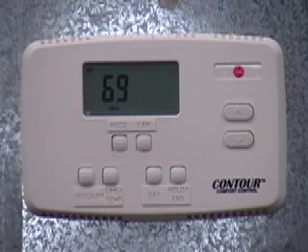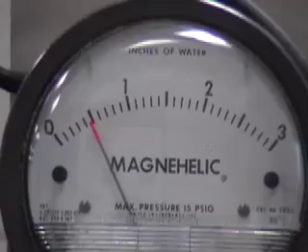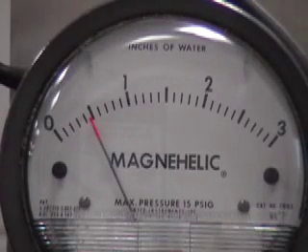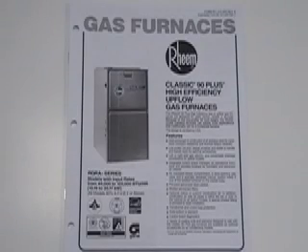Let's begin by putting the system into the cooling mode. As you can see, the Magnehelic gauge is registering 0.5 inches of water column total external static pressure. This equates to 1,200 CFM of airflow on this unit. Let's look at the blower performance chart for this unit.